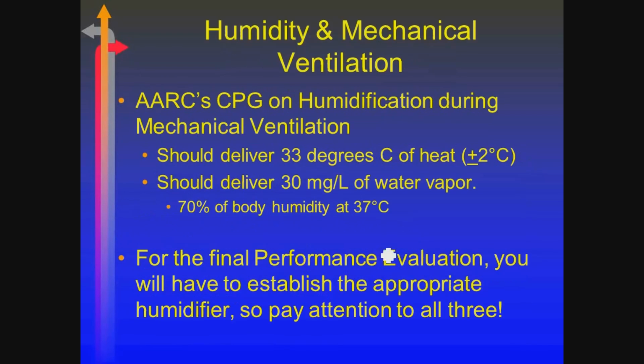And then humidification is another key part, because we're bypassing the natural airway, we want to humidify any gas. Key thing here are those two values, at least 33 degrees centigrade and at least 30 milligrams per liter of water, which equates to about 70% of body humidity at body temperature, which means that you still have some humidity deficit that the body has to compensate for. So that's kind of what the clinical practice guideline on humidification recommends.